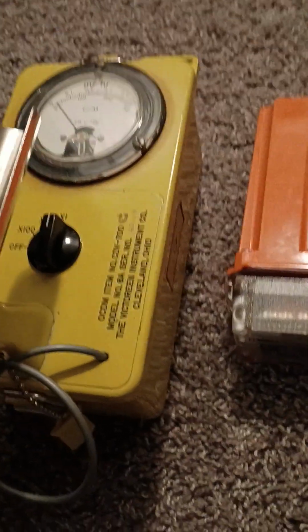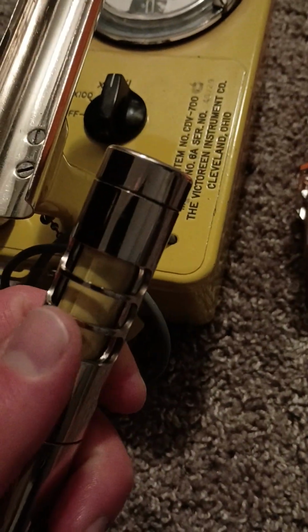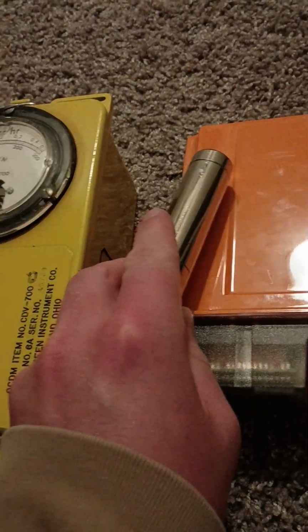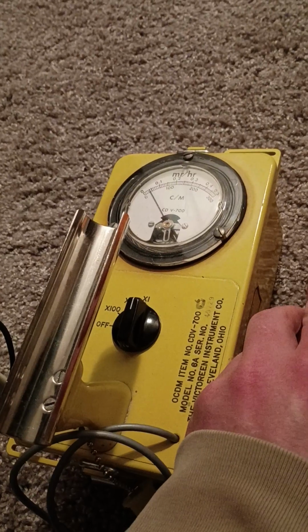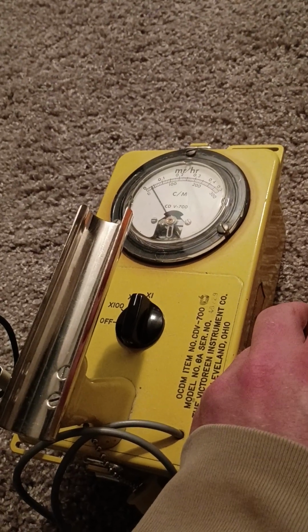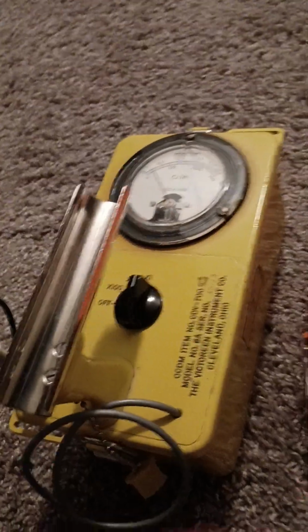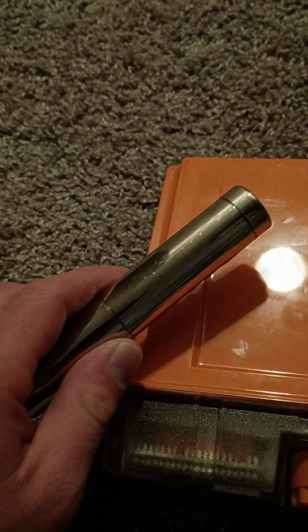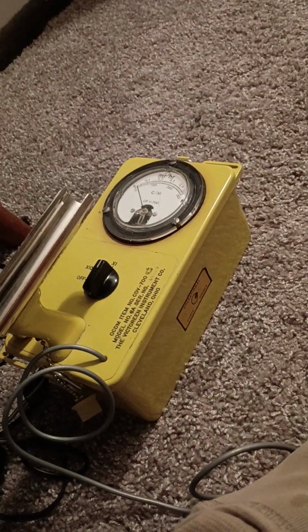Well, we are going to check it with the CDV 700 first. Beta shield is open. You can see the exposed glass of the Geiger-Muller tube right there. And put it right there. We have it on ×1. I actually am making quite a foolish thing here because the check source is right there, so I'm going to move that back a little bit. And even resting directly on it, on contact, there is no noticeable rise.